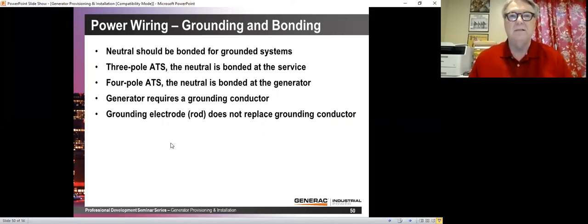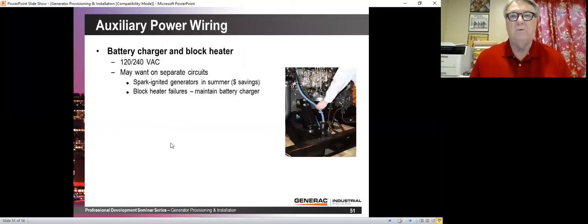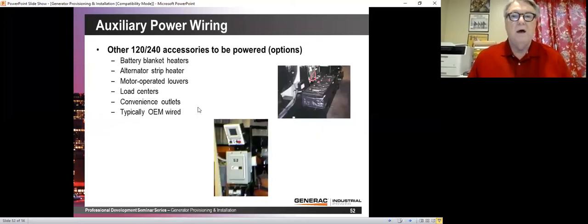ATS class. 3-pole ATSs, the neutral's bonded at the service. 4-pole ATSs, the neutral's bonded at the generator. Do not bond the neutral to ground at the generator if you have a 3-pole transfer switch. This is a picture of a block heater or a coolant heater, kind of the same thing, and that's what keeps your engines warm. Other accessories that you can have, here's a little load center.